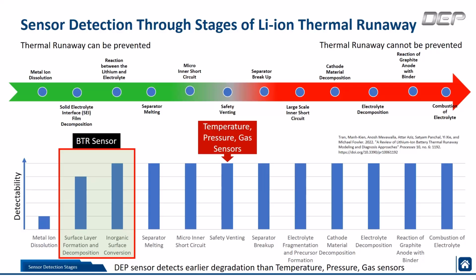Then the gas begins to vent. And due to this increase in the pressure from the gas formation, you have the separator completely melting at the next point, causing a large-scale internal short circuit. Then the short circuit leads to the decomposition of the cathode and the electrolytes. The decomposition of the cathode results in release of oxygen, which reacts with the electrolyte and can result in combustion. Decomposition of the electrolytes begins after this and releases more gas. Then you have the anode reacting with the binder material to increase the temperature more, and the last stage is where the combustion happens from the ignition of the gases.